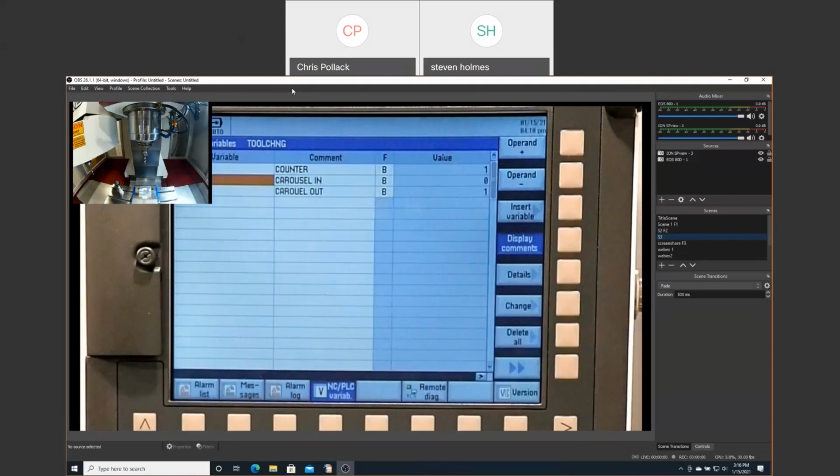You see how I said okay, mine immediately went back to a 1? That means in this case, the PLC is not letting me override it. But that's what that change button's for. I've run into cases where that was handy to just kind of fool the system into thinking it was a different condition to try to diagnose my problem.